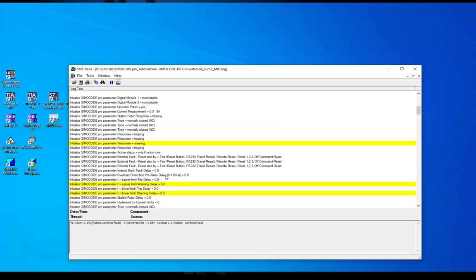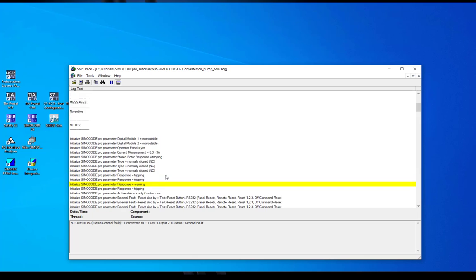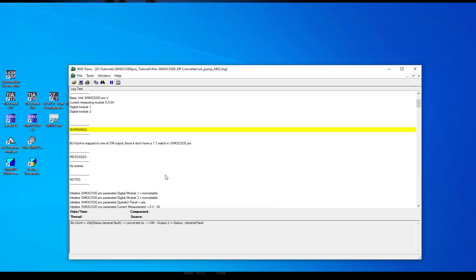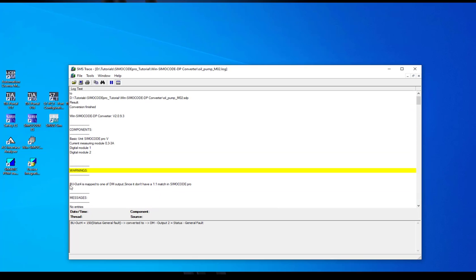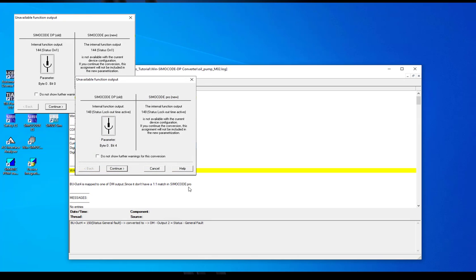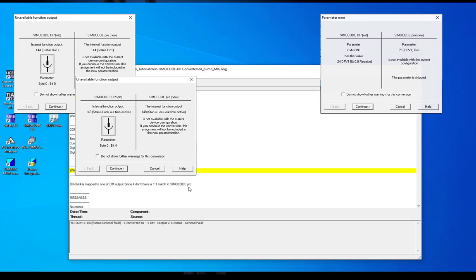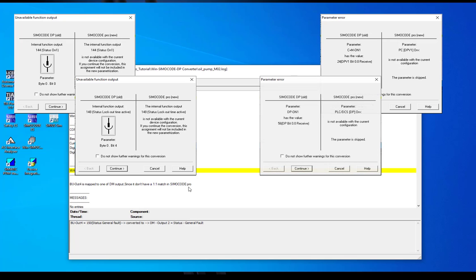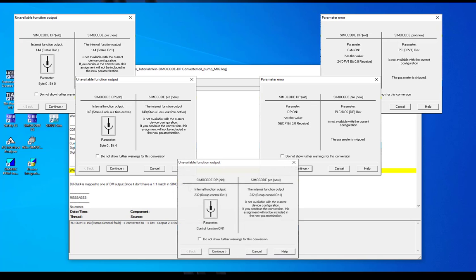At the top of the log file you will find an area for warnings. There it is also mentioned that the basic unit output was converted to an output of a digital module. When you convert a direct starter application from SimoCode DP to SimoCode Pro you will get some messages in relation to its parameters for the reversing starter. At SimoCode DP the reversing starter parameters were assigned but not used. At the SimoCode Pro system there are no longer the reversing starter parameters for the direct starter available.